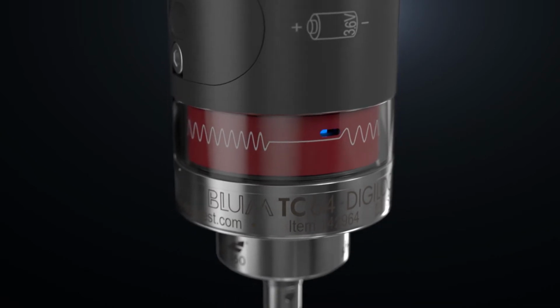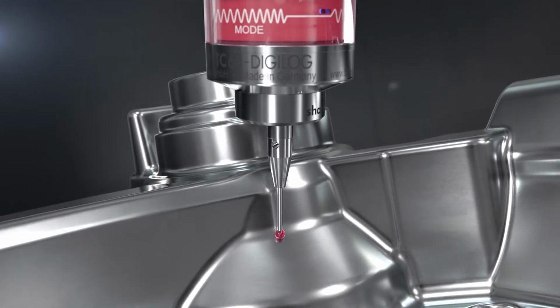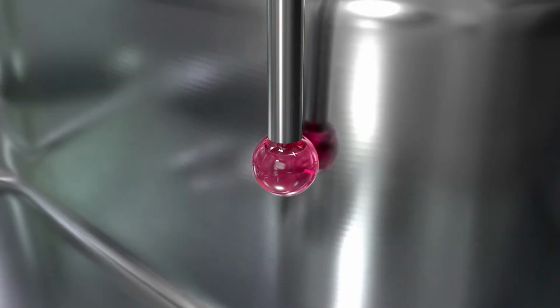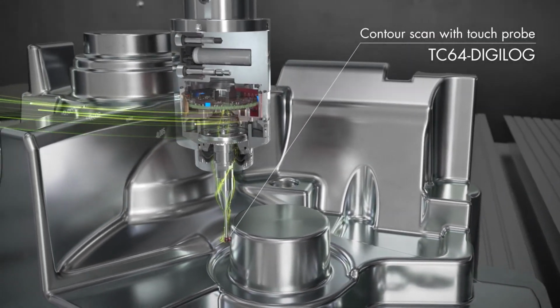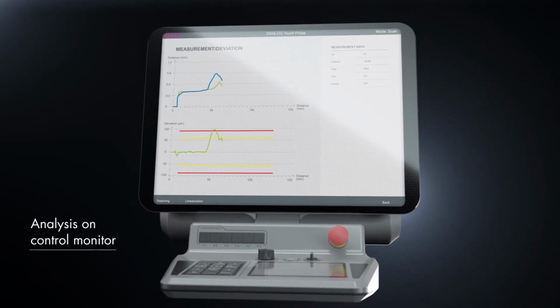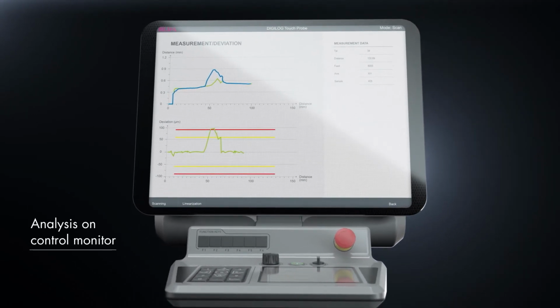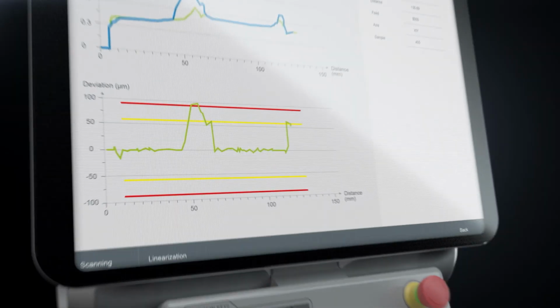The TC64 Digilog needs to be taught once at the outset on a good contour. The warning limit as well as the lower and upper tolerance limits are determined on the basis of the good contour. The measured contour is recorded and logged on the control monitor.